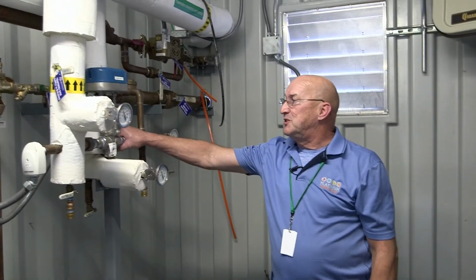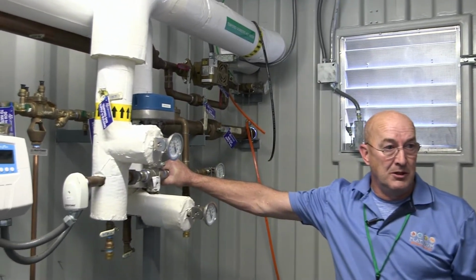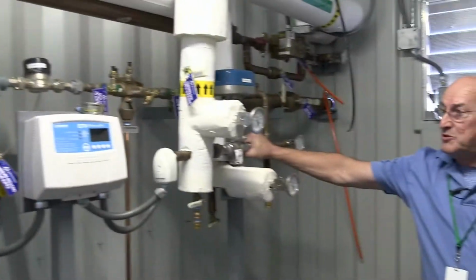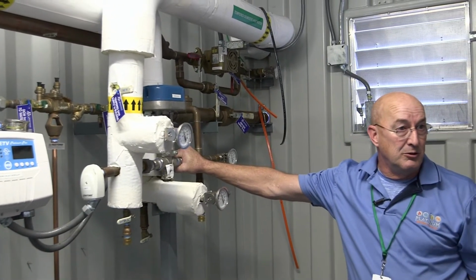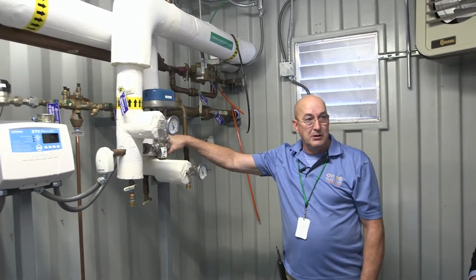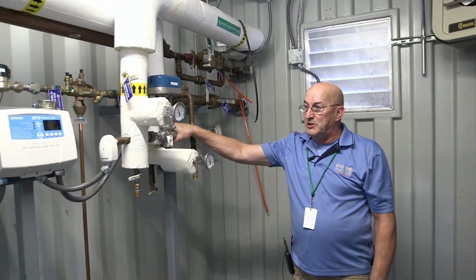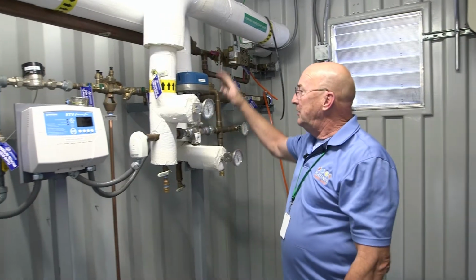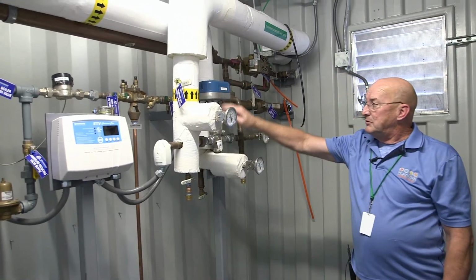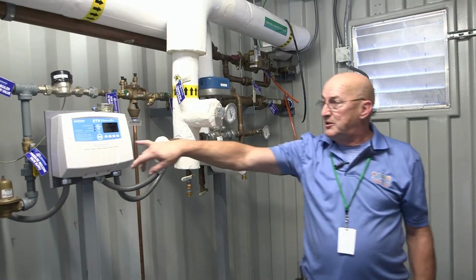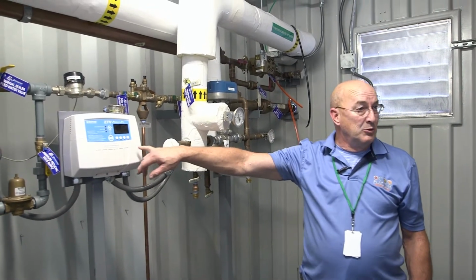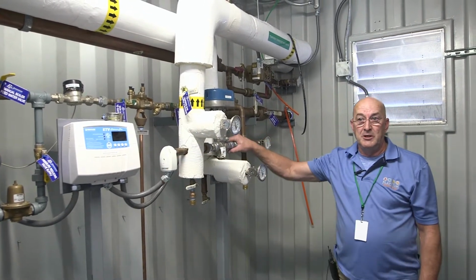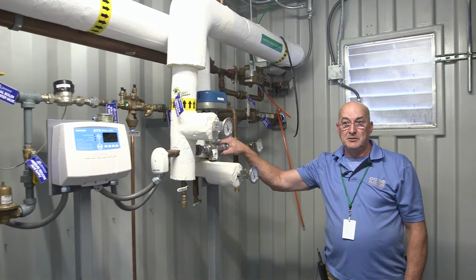We'll start off with this. This is your domestic hot water mixing station. This controls the temperature of the hot water throughout the building. I don't know what you have now, but this is what they call a heat timer or ETV control. This is the actual motor that modulates up and down according to the temperature this gets set at. We normally set them at 125. This meets city guidelines. It can be a little less if you're finding the water's good, or it could be a little bit more, depending on what you want it at.